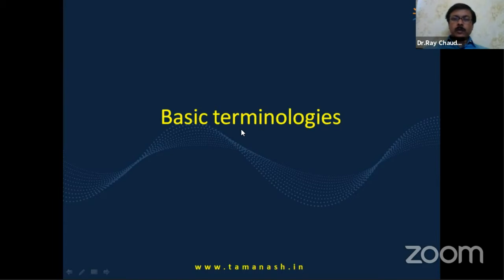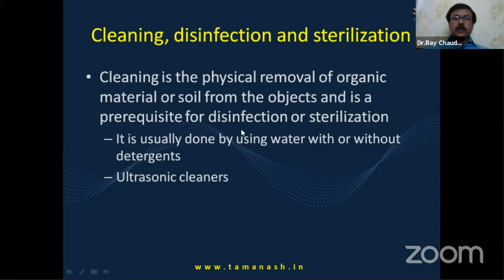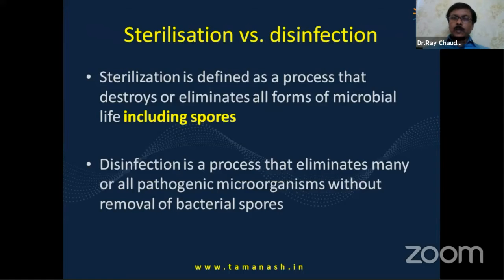Just a few basic terminologies to start with: cleaning, disinfection, and sterilization. Cleaning is the physical removal of organic soiling material and is a prerequisite for disinfection. As I'll be talking about later in this talk, removal of organic soil is very important for the sterilization process to be effective. It can be done, as Anshuman showed, using water with or without detergents, and ultrasonic cleaners.